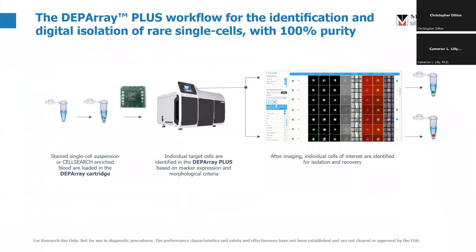What does the workflow look like from a 10,000-foot view? Basically, you prepare your cell suspension — that goes into the DEPArray cartridge. The cartridge then goes into the instrument itself. From there, these cells are put into the middle chamber, trapped and imaged from the image gallery. You then pick the cells that you want, tell the instrument how you want to isolate them, and they come out the other side 100% pure. This can be either single cells or pools of identical cells as well.